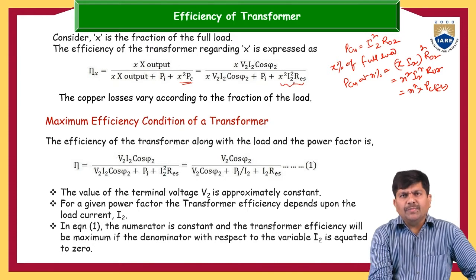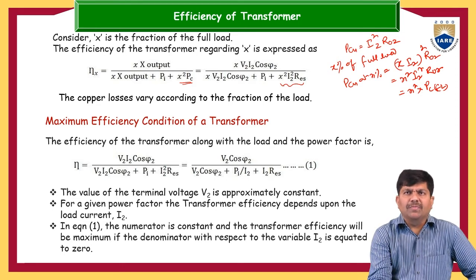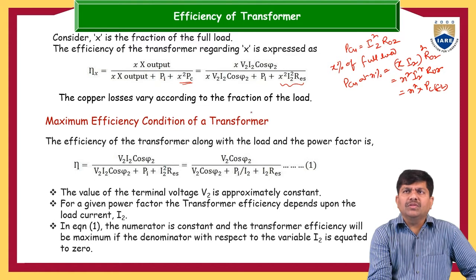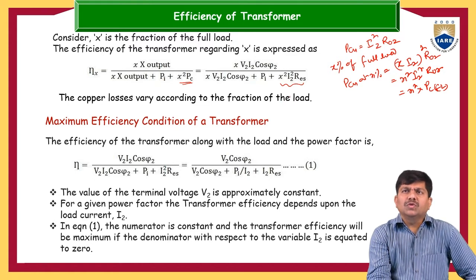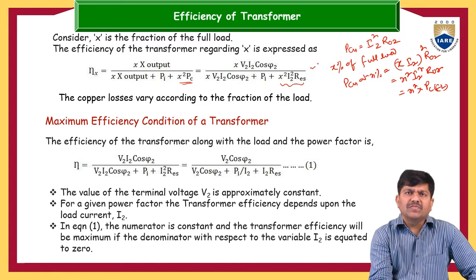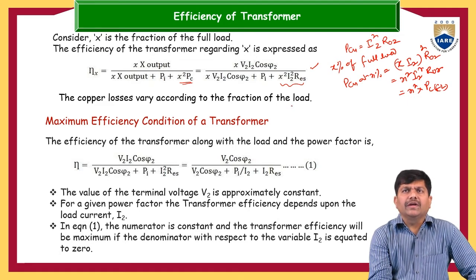So copper losses change in proportion to the load, whereas iron losses remain the same. The copper losses vary according to the fraction of the load. This is a very important expression, useful for calculating efficiency at various loading conditions.